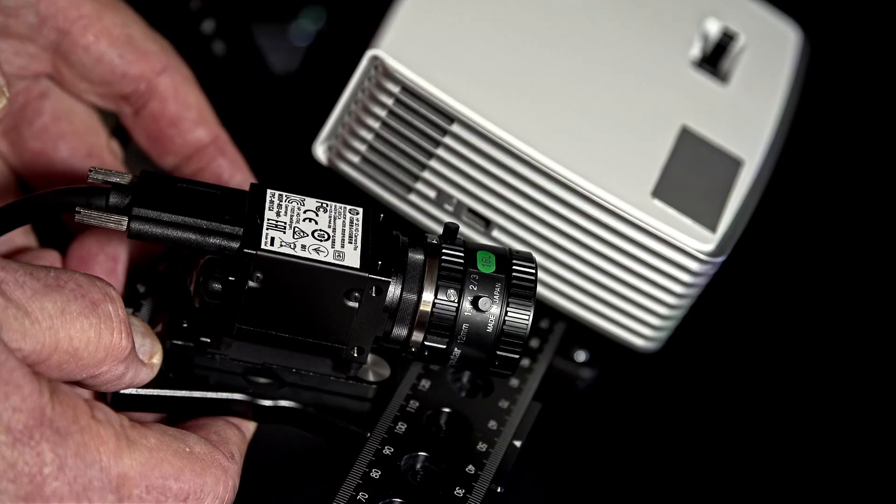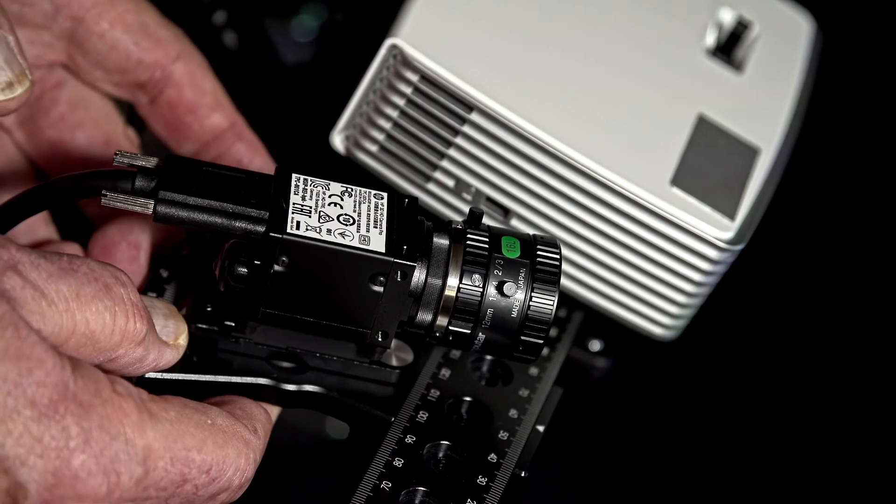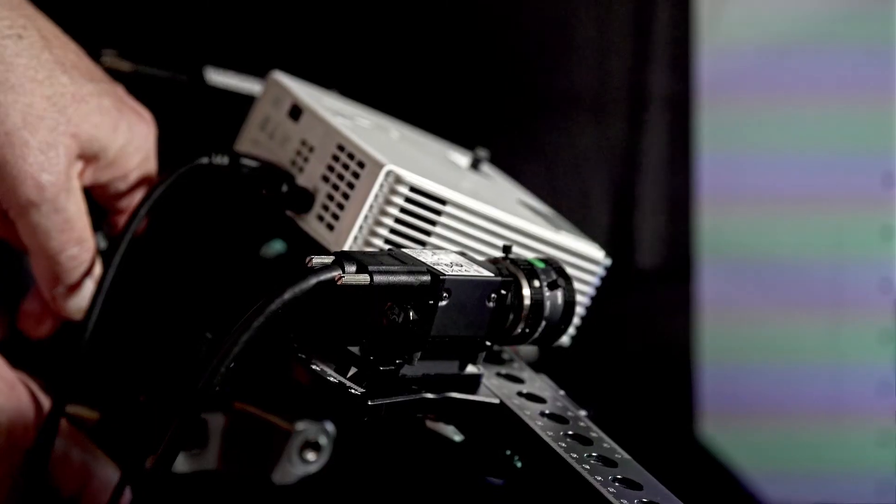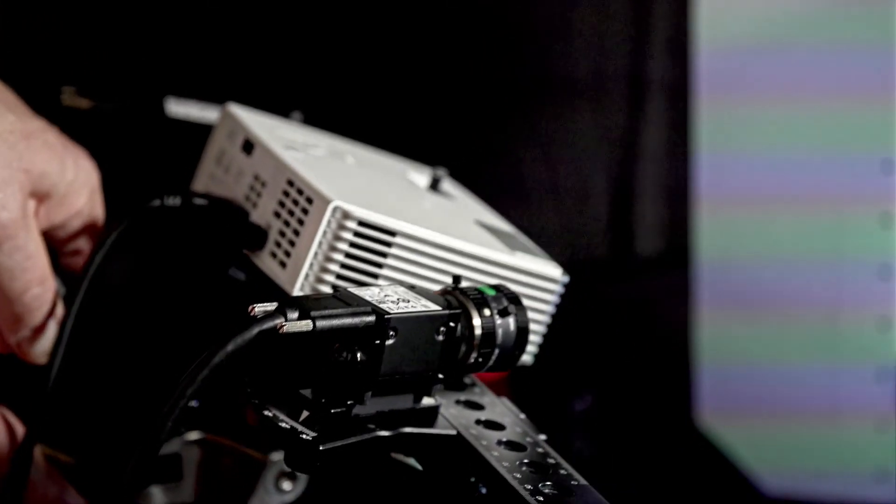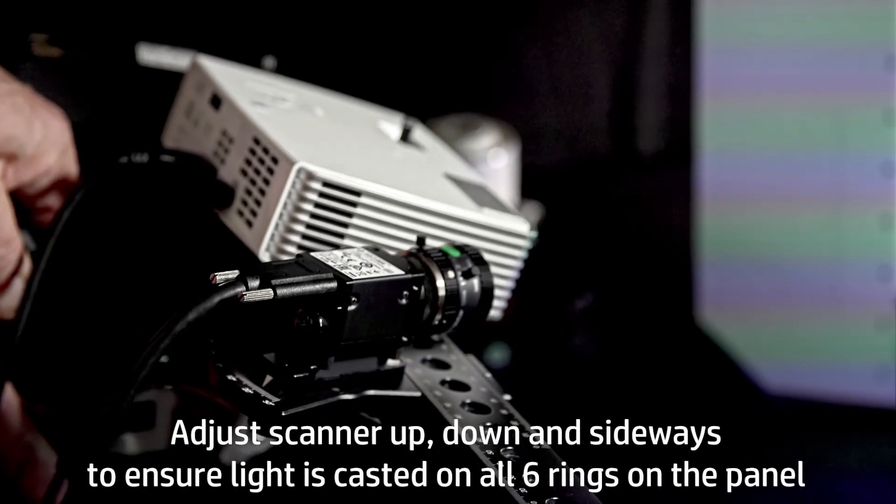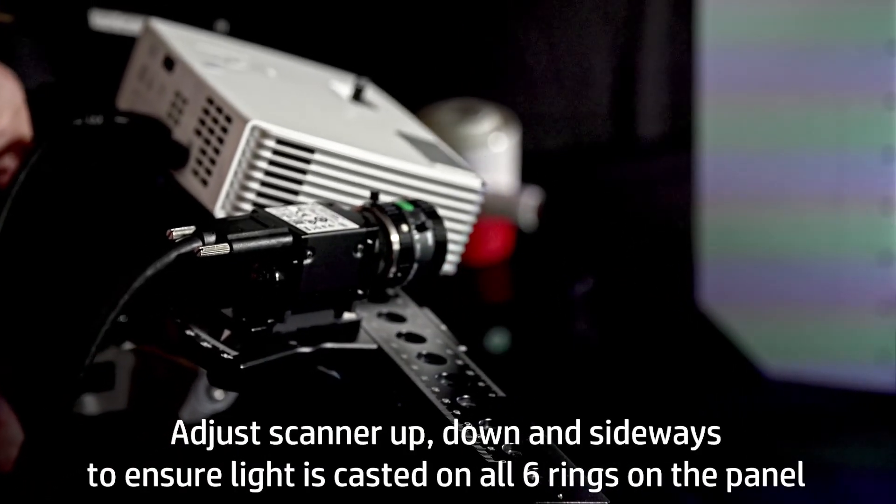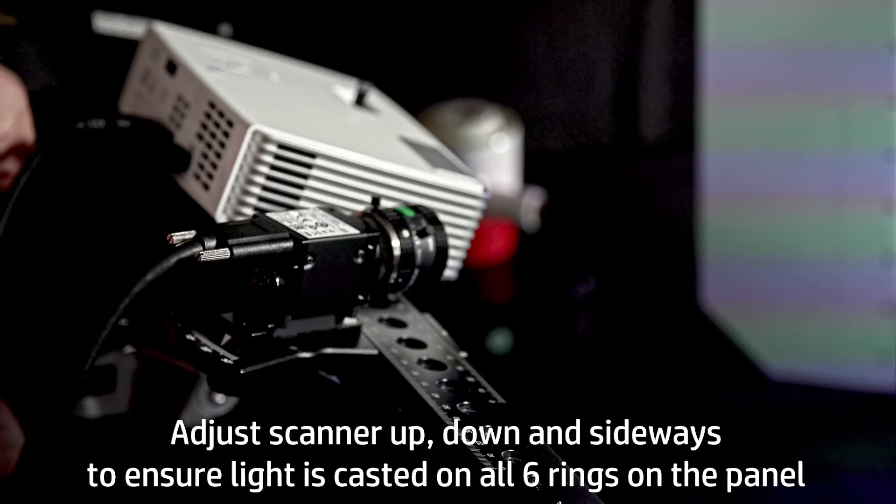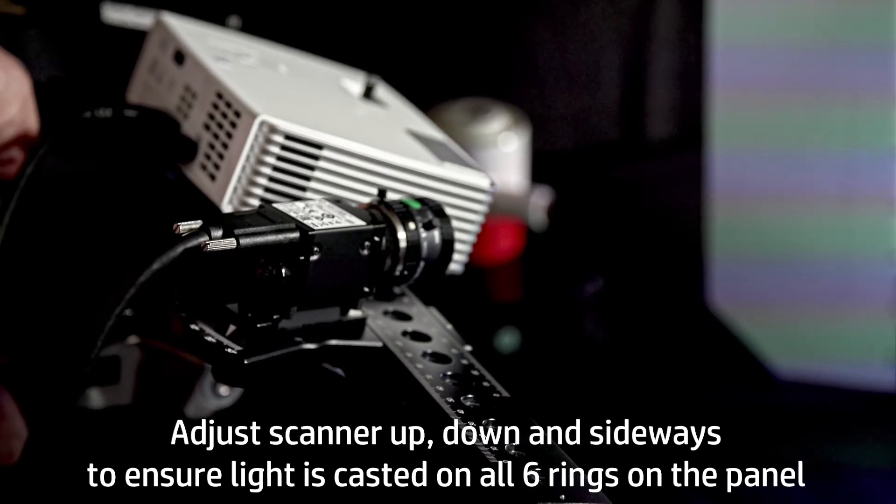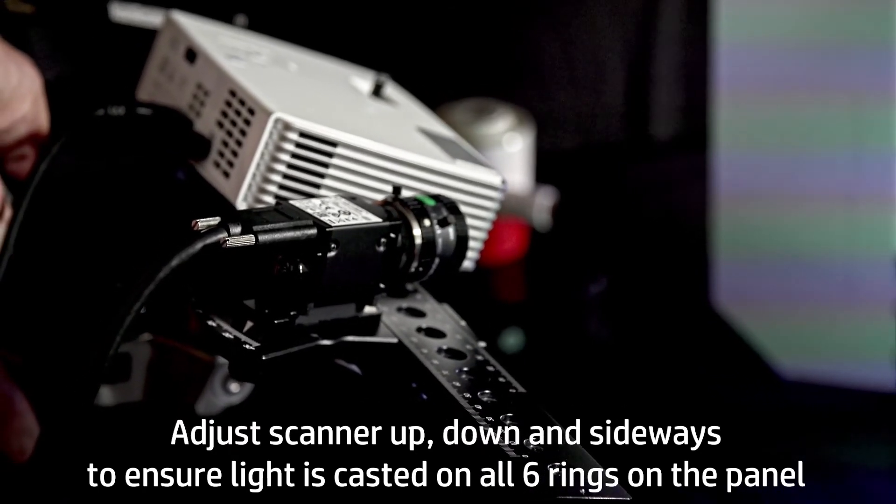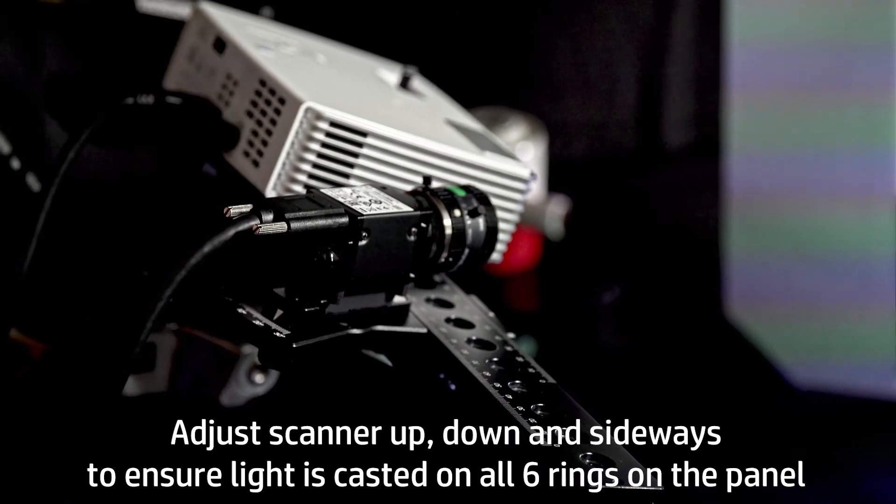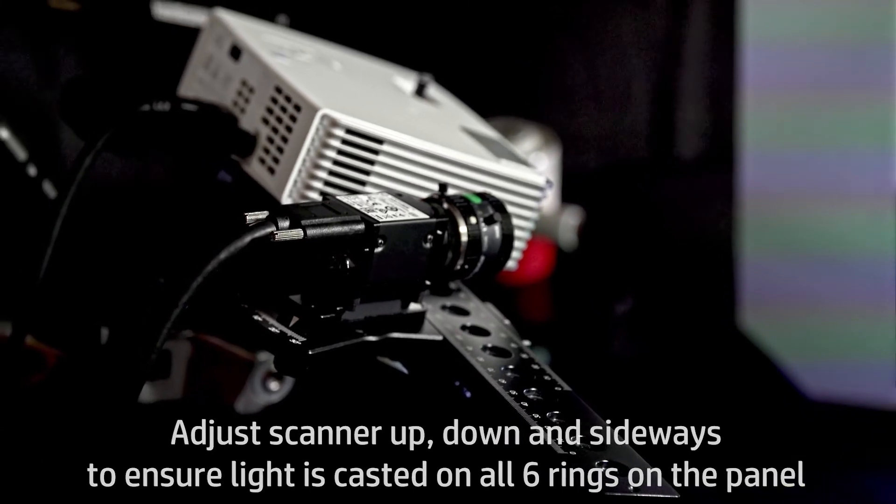Most of the time, you will need to do some minor repositioning of the scanner to get a good calibration. Moving the scanner vertically or horizontally to maximize the light pattern on the panel will be helpful. Avoid changing the distance between the scanner and the panel, however.